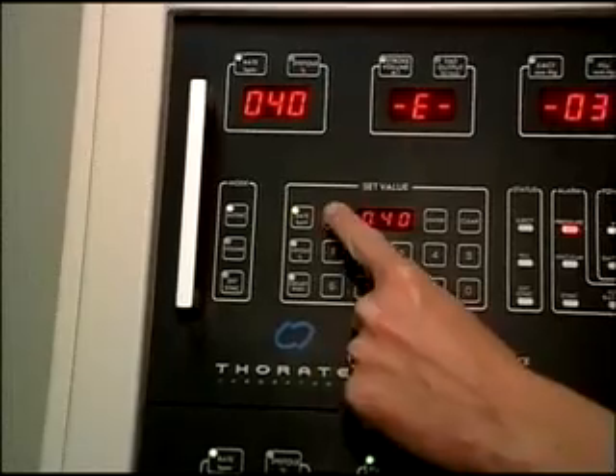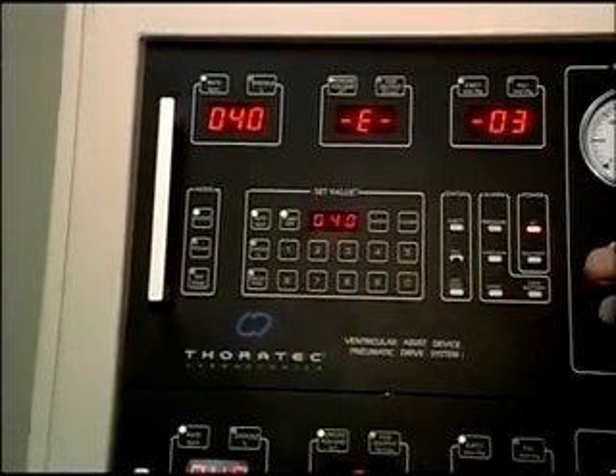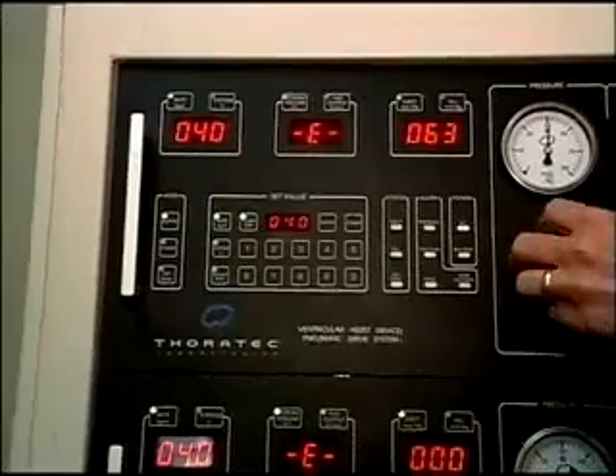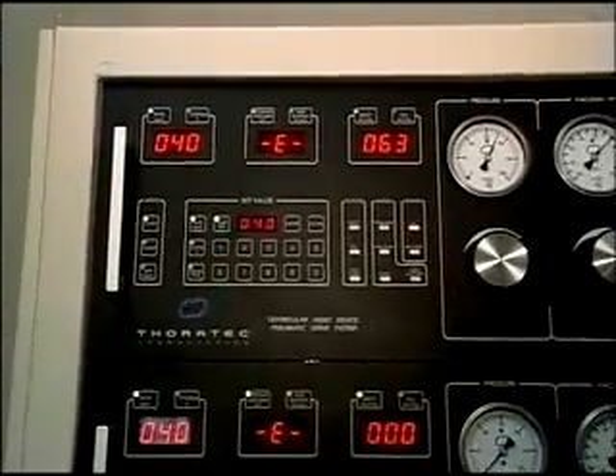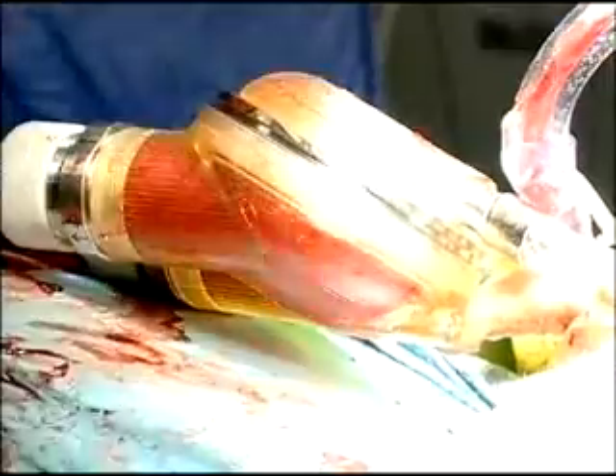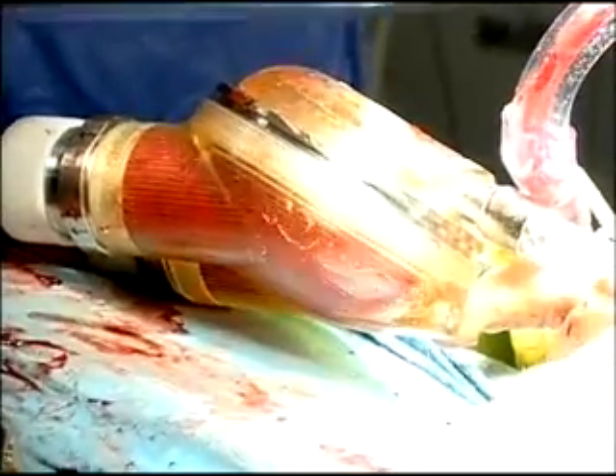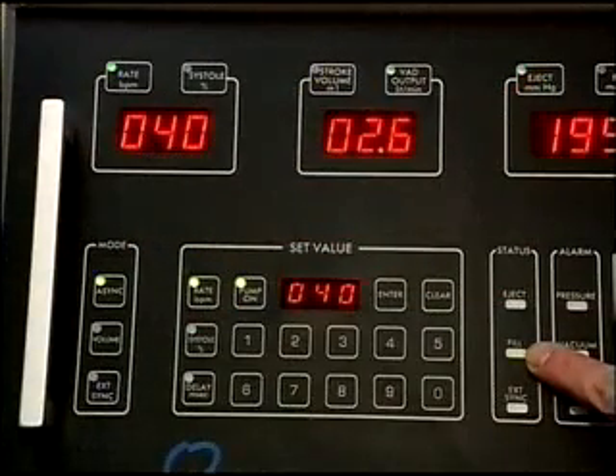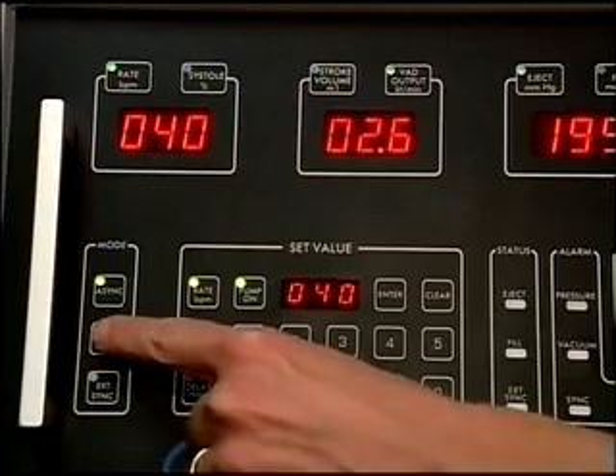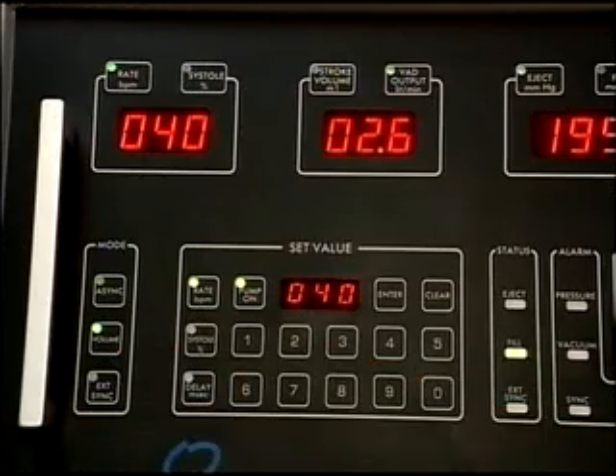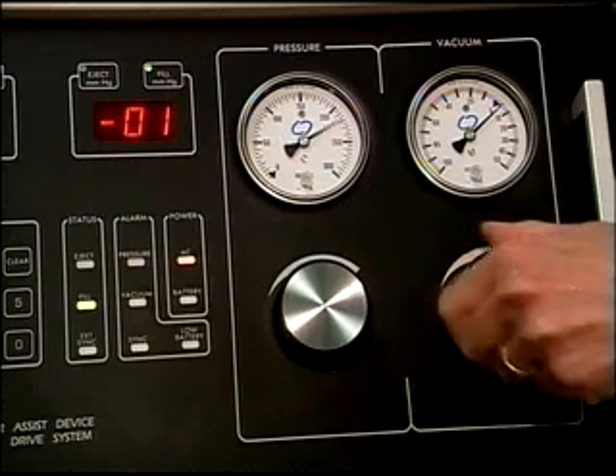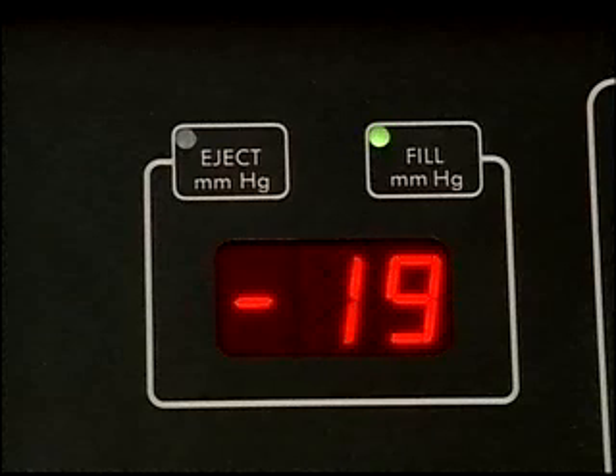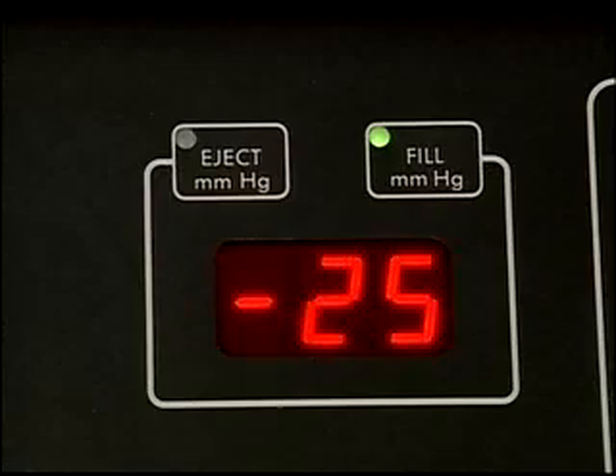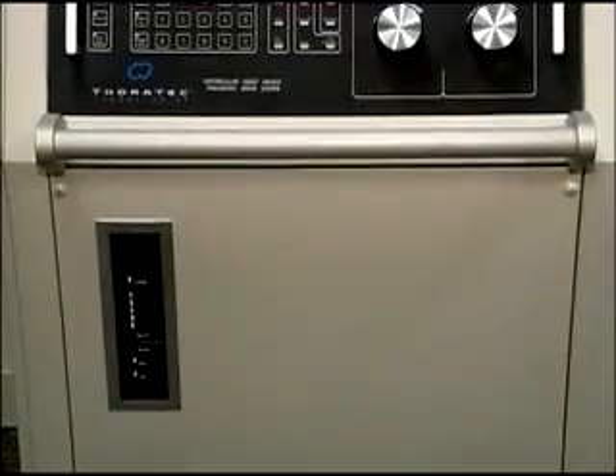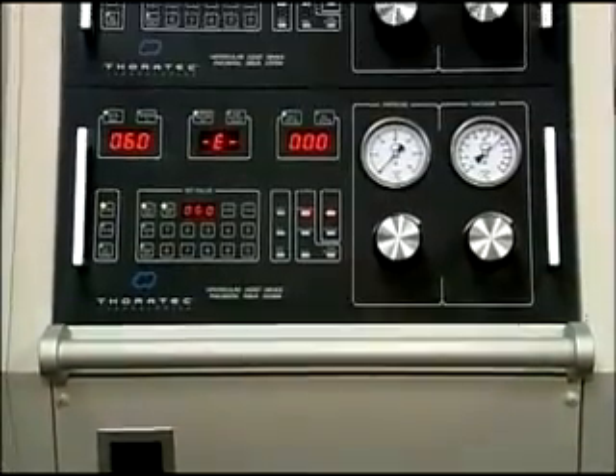When directed by the surgeon, press pump on, then gradually increase the eject pressure until the VAD is ejecting completely. This can be verified by a flash of light resulting from the two sides of the VAD blood sac touching. Once the VAD is filling and emptying at 40 beats per minute in the asynchronous mode, operation can be switched to the volume mode. Vacuum can be adjusted up to -25 millimeters of mercury while the chest is open to assist VAD filling. This concludes the startup procedure for the dual drive console.